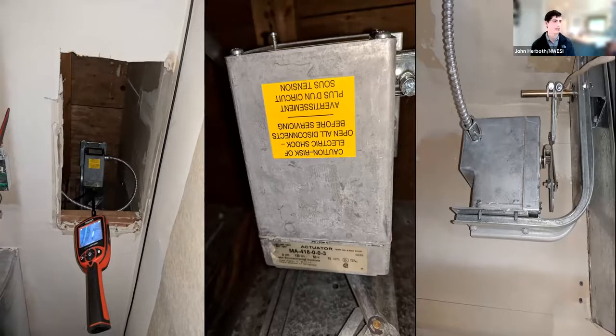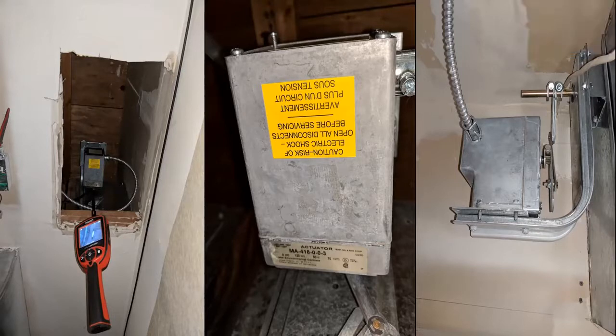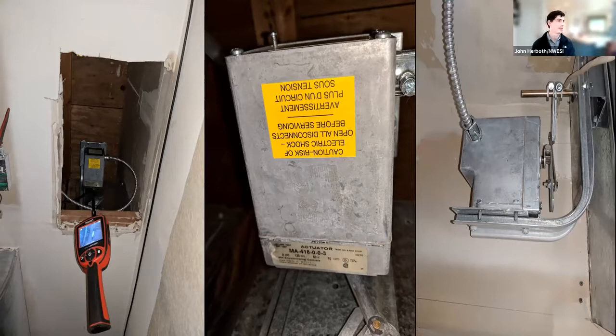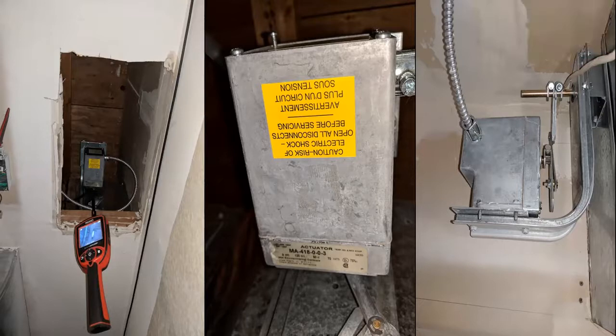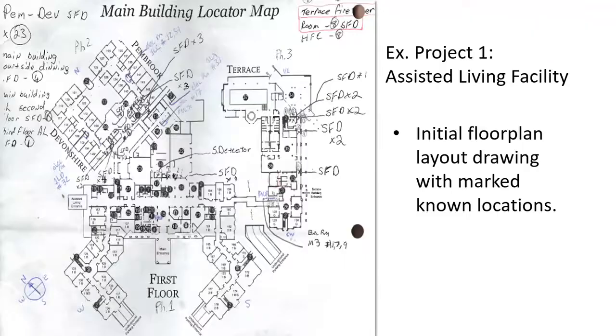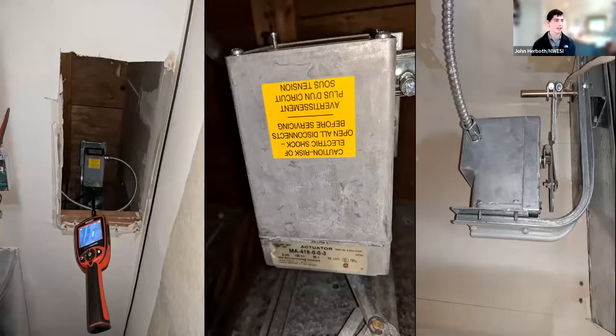Larry, there are quite a few recalls out there from damper manufacturers, aren't there? There's only one. Oh. The Barber-Colman CBs were recalled by the Consumer Product Safety Commission in 2002. I stand corrected. One. Do they pay for a new one or anything on those? No. So that's a quick no. But there were multiple models that had problems. And if you see this block, you're going to have a few manufacturers, and from Larry's replacement guide, there are several that are branded differently for the same style.